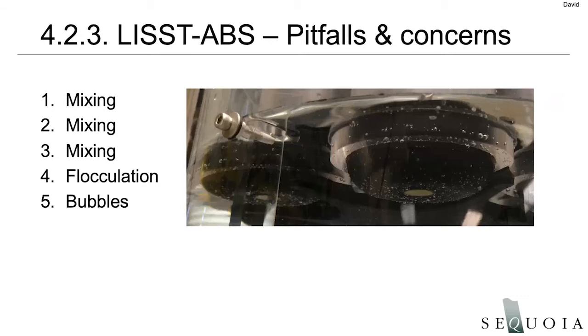Pitfalls and concerns. Any of you who have tried handling larger suspended particles in the lab know that it is challenging to get them properly mixed. In our particular setup, we've worked out standards that give us repeatable results. There's kind of a delicate balance, actually, between mixing speed sufficient to keep things suspended versus introducing bubbles. Bubbles definitely will affect the reading. They tend to depress the readings because the bubbles, at least if bubbles are clinging to the instrument, as they are in this picture shown on this slide, they tend to diffuse the signal coming from the transducer, and they tend to make it weaker. So they depress the apparent concentration.